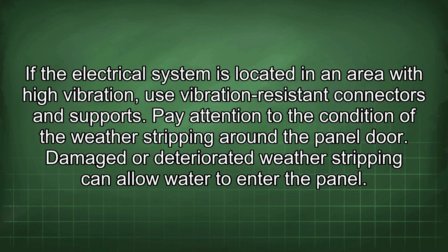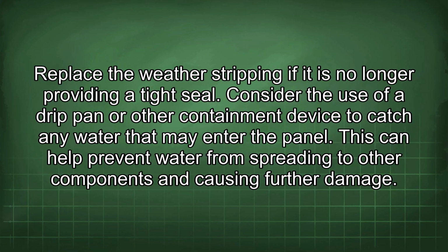Pay attention to the condition of the weather stripping around the panel door. Damaged or deteriorated weather stripping can allow water to enter the panel. Replace the weather stripping if it is no longer providing a tight seal. Consider the use of a drip pan or other containment device to catch any water that may enter the panel. This can help prevent water from spreading to other components and causing further damage.